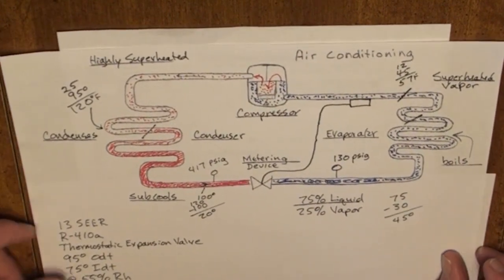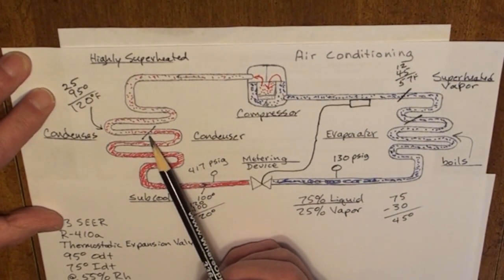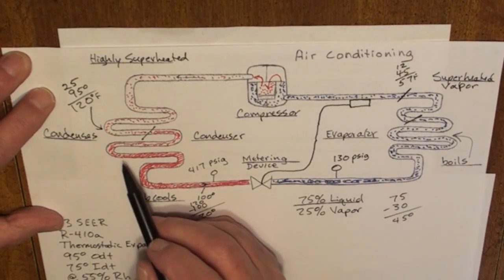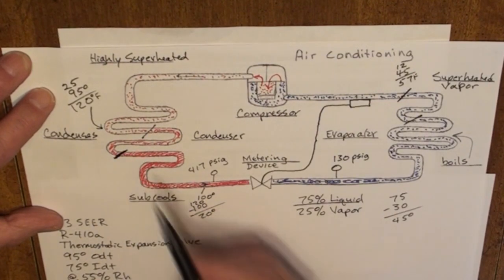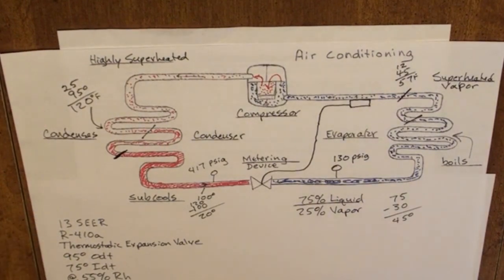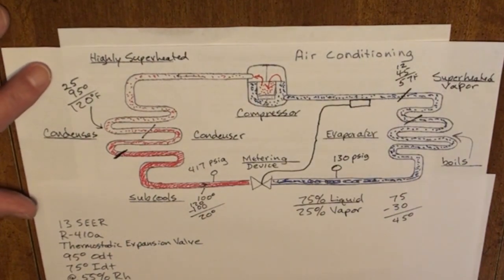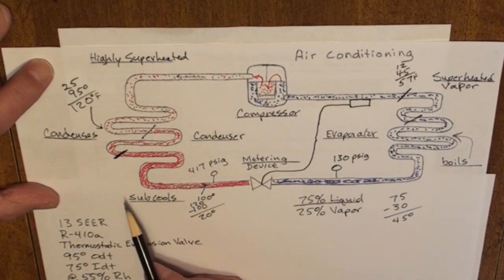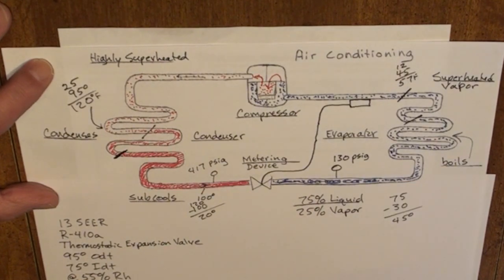Subcooling is defined as the temperature of a liquid refrigerant when it's cooled below its condensing temperature. Here, the refrigerant condenses back into a liquid, and once we have no more vapor, the refrigerant gives off sensible heat below the condensing temperature. A properly charged system on a 95-degree day would give us 20 degrees of subcooling.